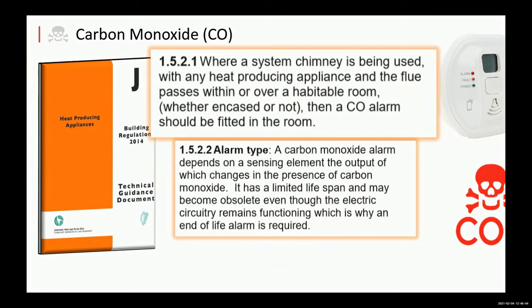So if we look here at 1521, where a system chimney is being used with any heat producing appliance, and the flue passes within or over a habitable room, whether encased or not, then a CO alarm should be fitted in that room.